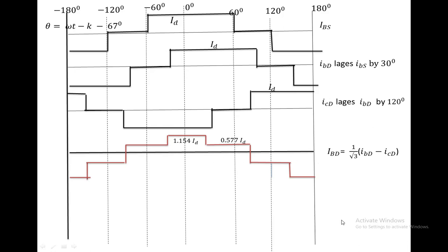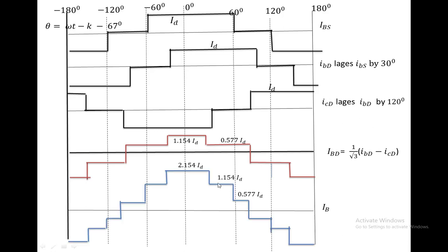Ultimately, IB equals the sum of the IBS waveform and the IBD waveform. Adding these two waveforms at every instant gives the IB waveform. If we observe this IB waveform, it has both steps and is almost a sine wave, near to the sine wave. Applying Fourier analysis, the harmonics in this phase B current will be less than the harmonics in the phase B current with a 6-pulse converter.